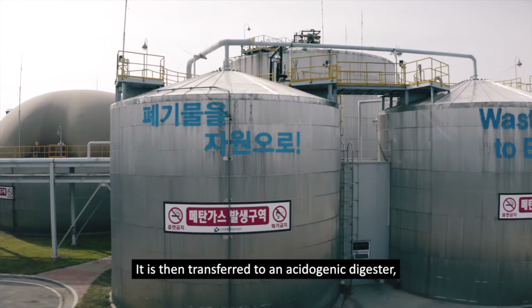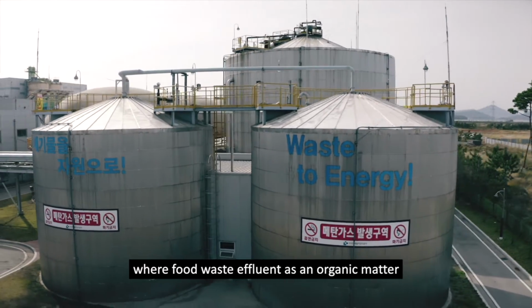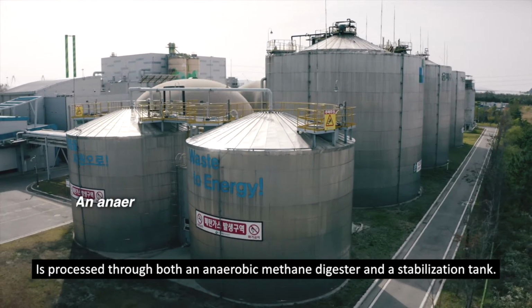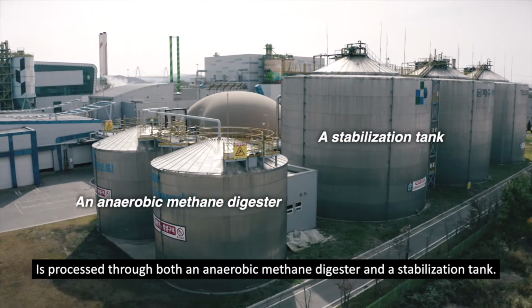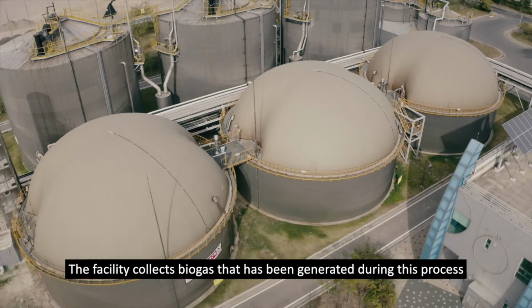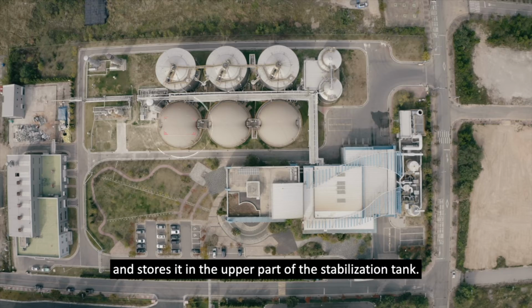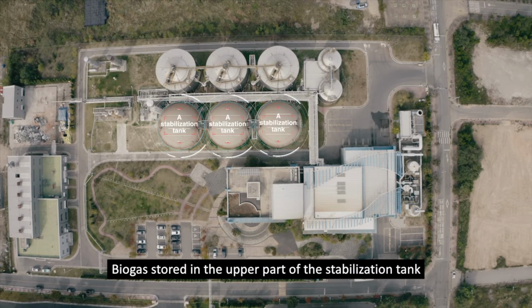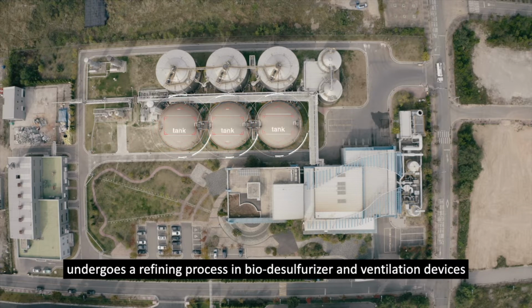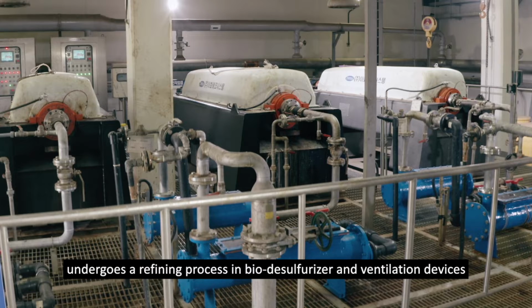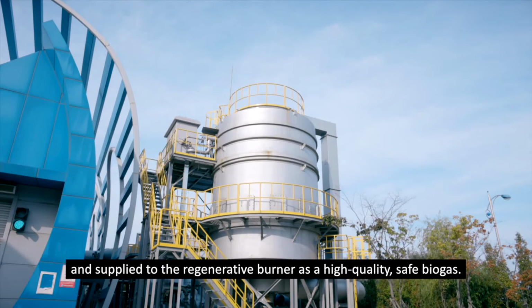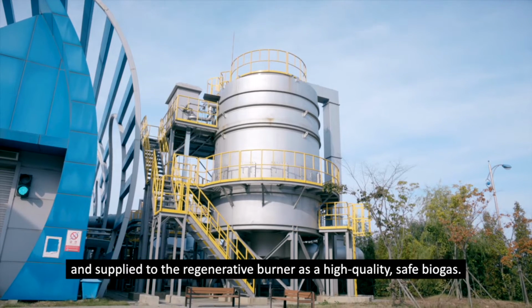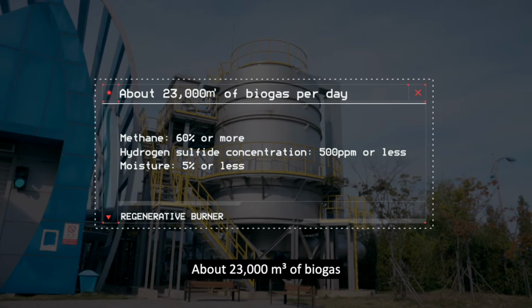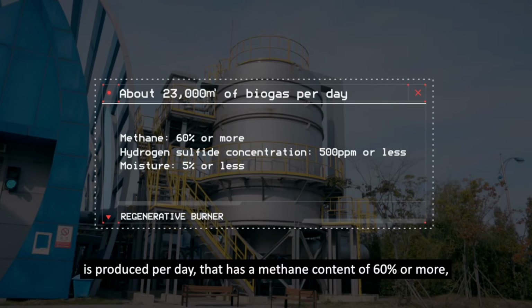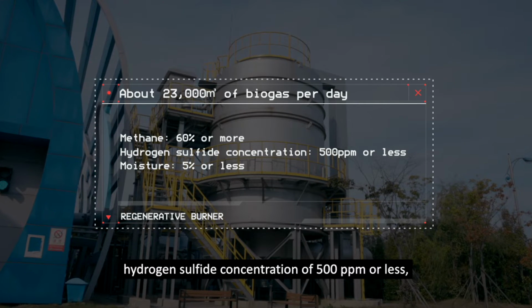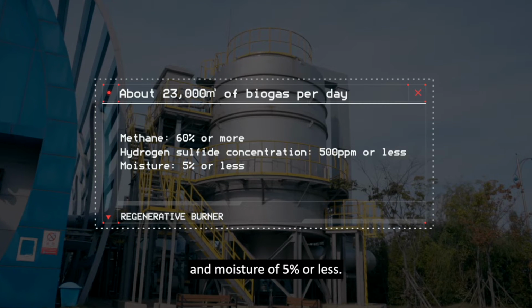It is then transferred to an acidogenic digester, where food waste effluent as an organic matter is processed through both an anaerobic methane digester and a stabilization tank. The facility collects biogas that has been generated during this process and stores it in the upper part of the stabilization tank. Biogas stored in the upper part of the stabilization tank undergoes a refining process in biodesulfurizer and ventilation devices, as well as biogas dehumidifiers, and is supplied to the regenerative burner as a high-quality safe biogas. About 23,000 cubic meters of biogas is produced per day that has a methane content of 60% or more, hydrogen sulfide concentration of 500 parts per million or less, and moisture of 5% or less.